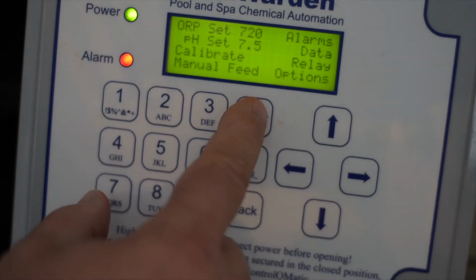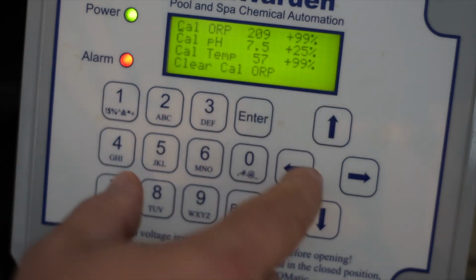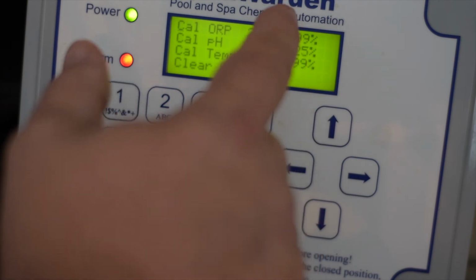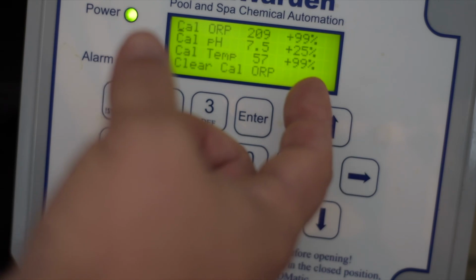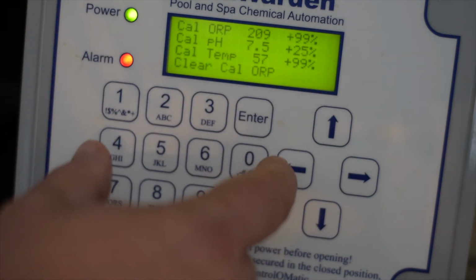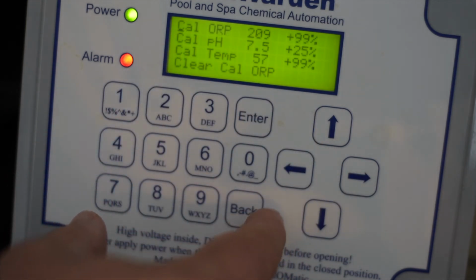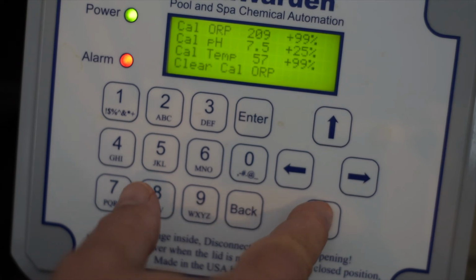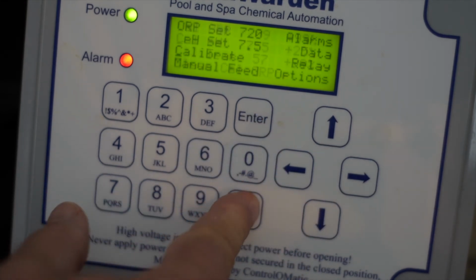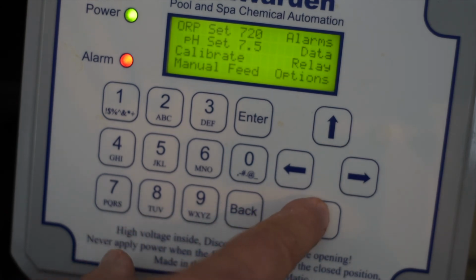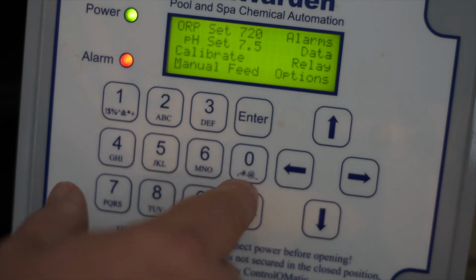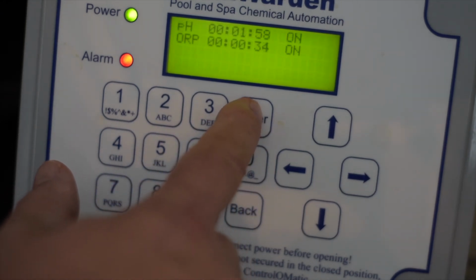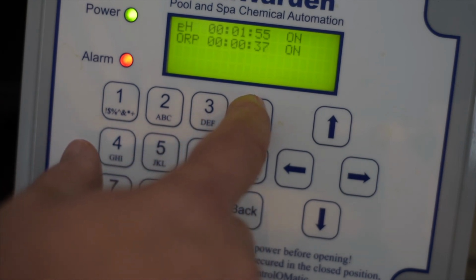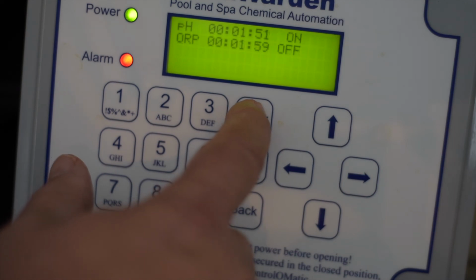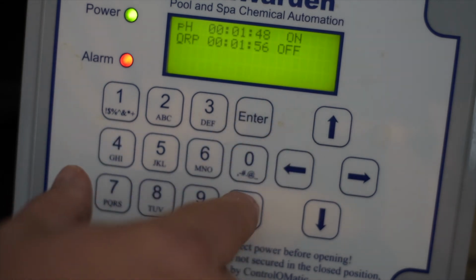Okay, and then we can also go into service. If we need to service and calibrate, we can go in here, and these numbers here, the percentage, are how much it's calibrated against the probe. Since there are no sensors, these are 99%, so normally that would mean you had a bad probe or something. You can also clear the calibrations, and manual feed will just initiate a 1 minute feed cycle. Actually, 2 minutes on here, and 2 minutes there. And then it goes back into automatic operation.